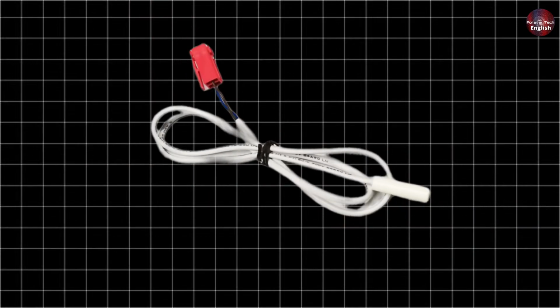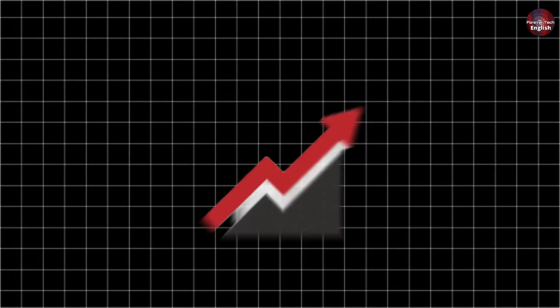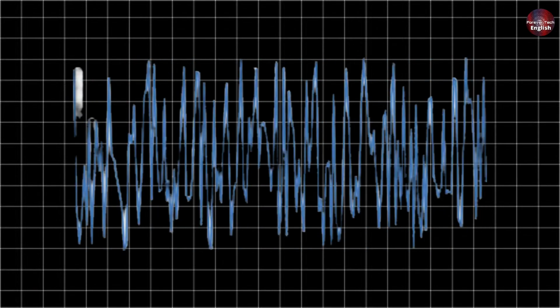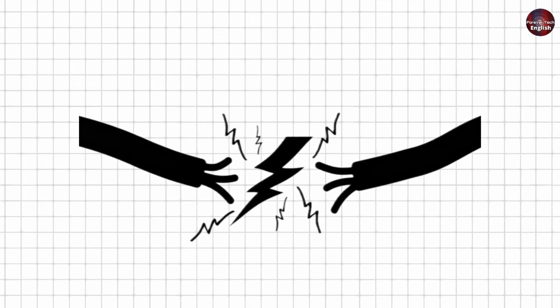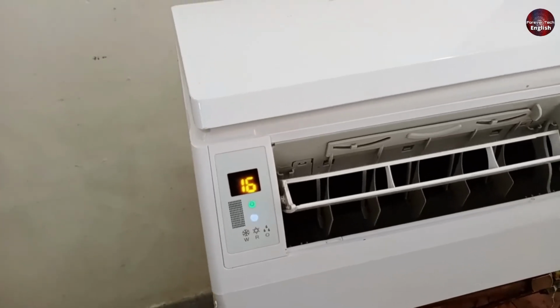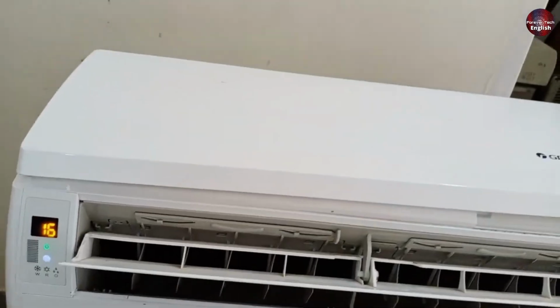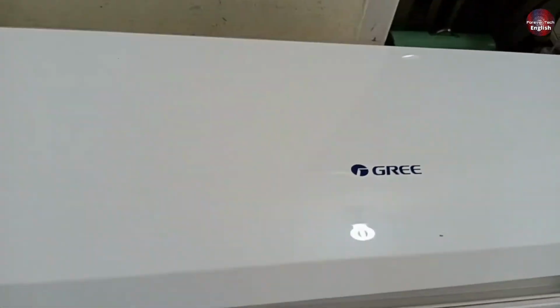However, if the sensor shows low resistance at one temperature, then suddenly high, then low again, or fluctuates between medium values, it means the sensor is shorted and needs to be replaced. Once you replace the sensor, the F5 error will disappear from the display and your unit will return to working condition.